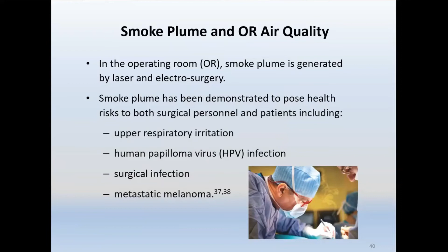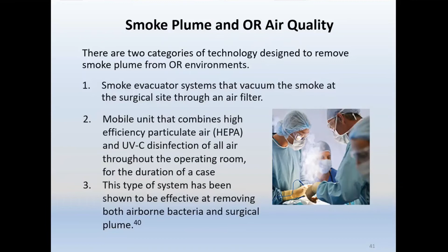There's also a very unique, one-of-a-kind mobile unit that you can move into the operating room that has high efficiency particulate air, or a HEPA filter, with UVC disinfection that will take all of the air throughout the operating room. It will purify it through the HEPA filter and UVC and disinfect it, creating a safer environment in the operating room. This type of system has been shown to be effective at removing both airborne bacteria and the surgical plume.